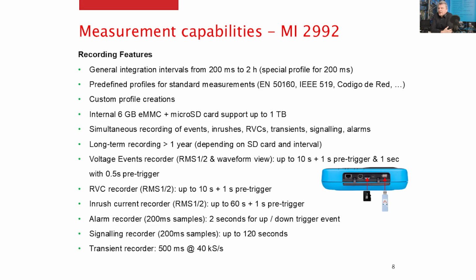Voltage events, so dips, swells, interruptions, are presented with RMS half-cycle samples and a waveform view. So it means waveform samples which are sampled with a frequency of 40 kilohertz. For the RMS preview, we can record up to 10 seconds with 1 second pre-trigger. But for a waveform, it's only 1 second with half a second of pre-trigger. This is because of the huge data which will be created, which would record 10 seconds. So each record normally takes about 600 megabytes of memory.